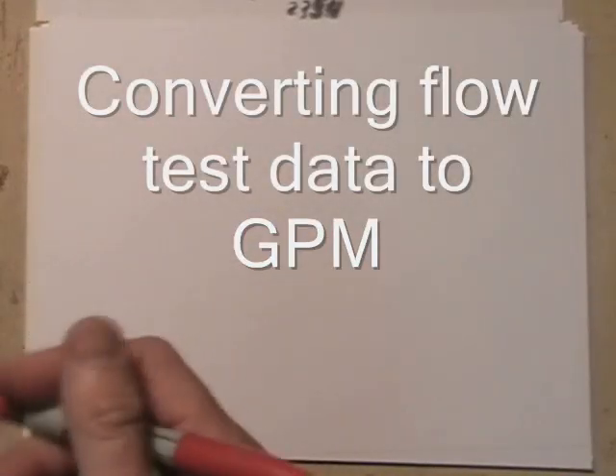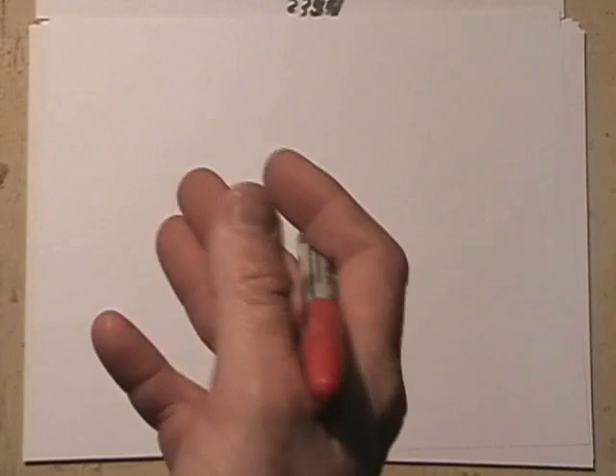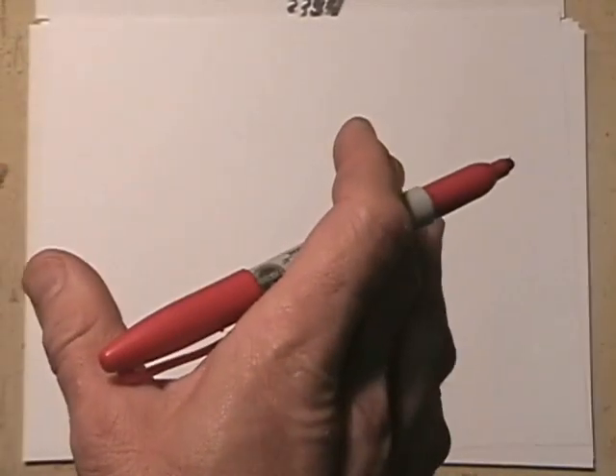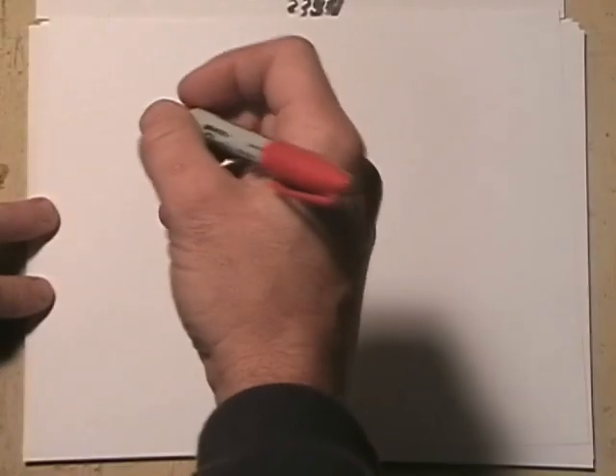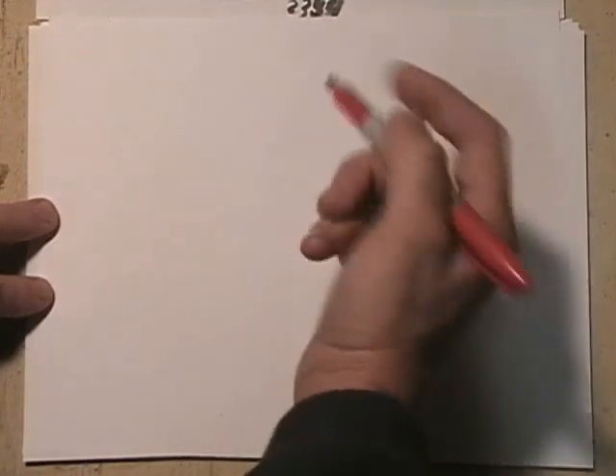This formula is a very popular formula for calculating fire hydraulics. You'll use this one even after you're in the service. It can be used for flowing hydrants, for checking the gallons per minute out of a hydrant. It can also be used for water shuttles or pump tests to know gallons per minute. So anytime you have an open orifice with water coming out where you can get a flow pressure from a pitot gauge, then you will be able to tell how many gallons per minute.